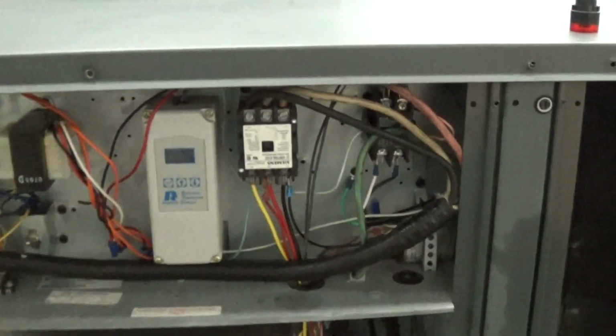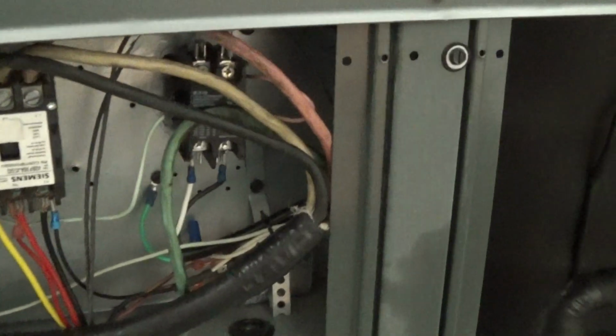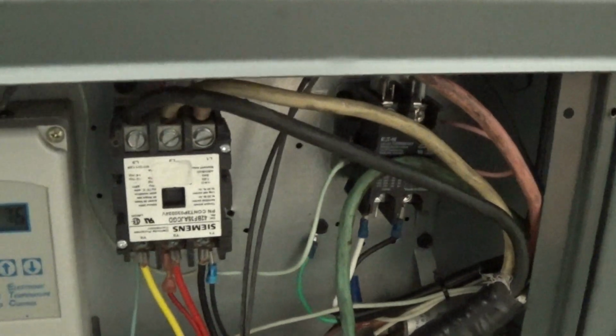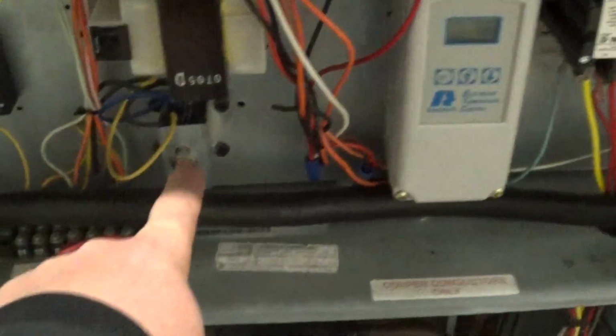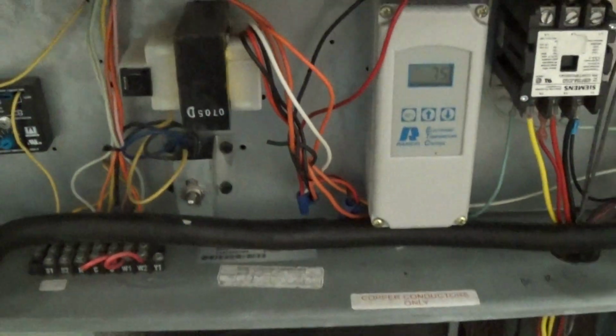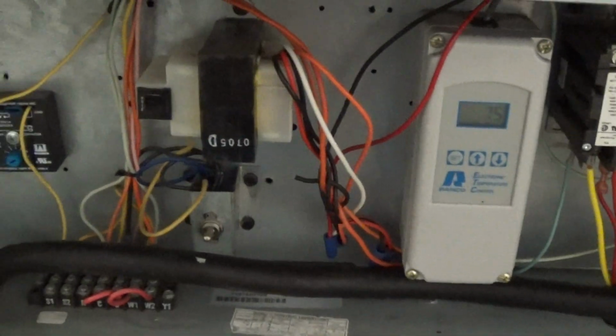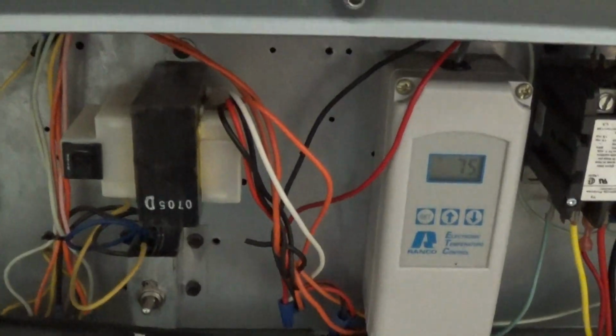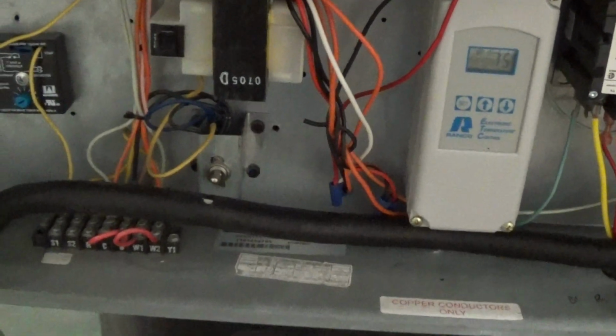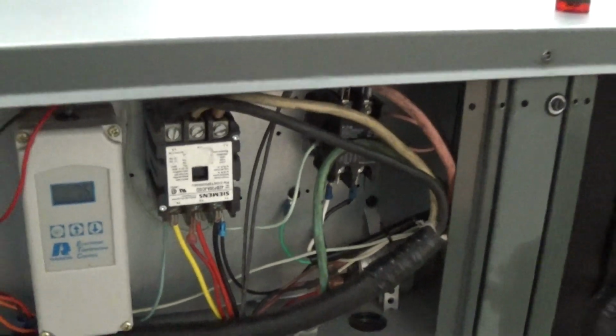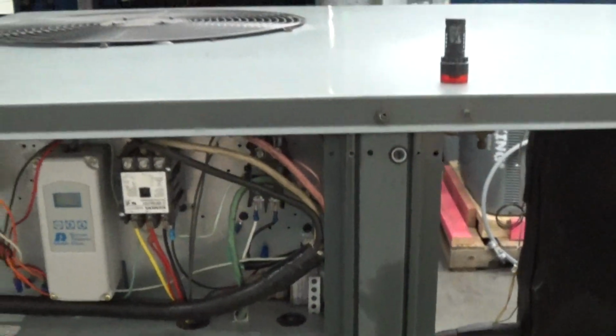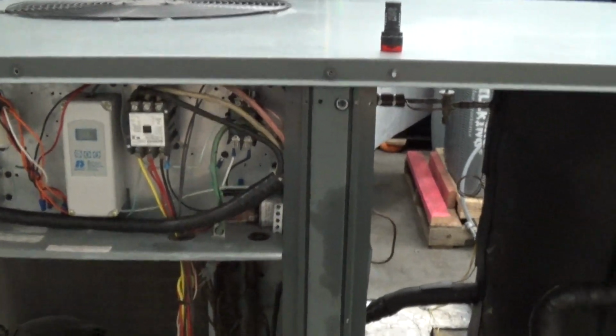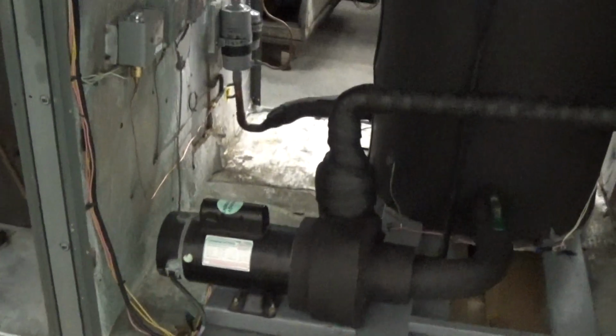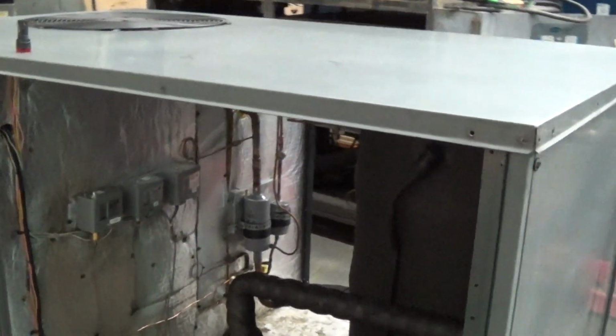So you basically have your Ranco temperature controller there. You have your primary contactor. All you have is this toggle switch for on and off power. Once you set that, it's set. Pretty much walk away. You have your controller transformer there. But really all you have to worry about is that incoming power, the phase rotation, putting it on a nice level surface, and go to town and start making some product.